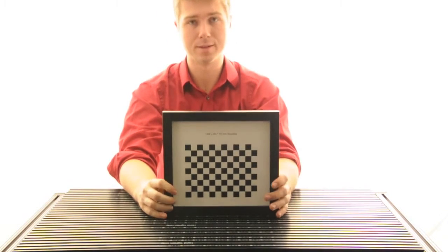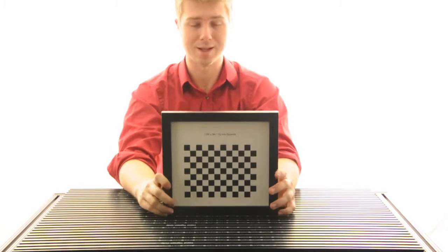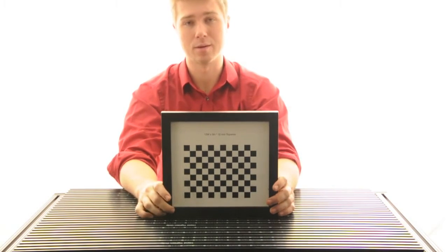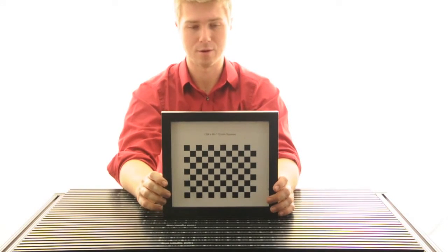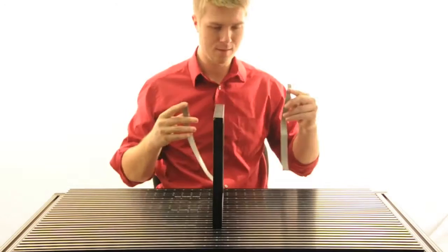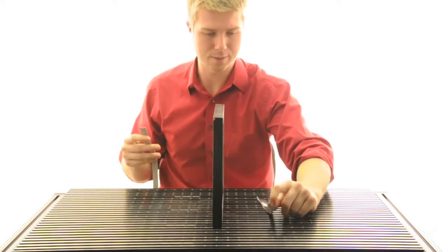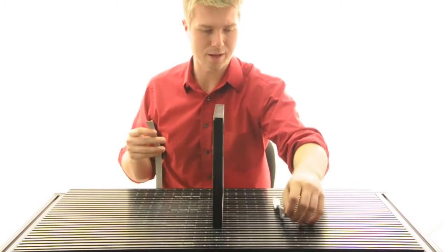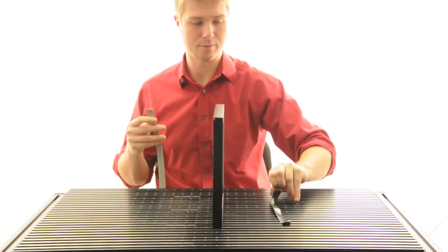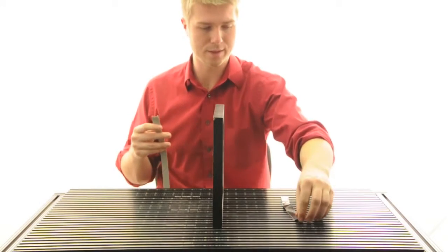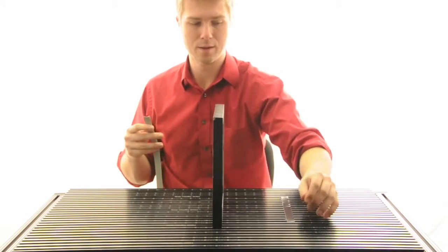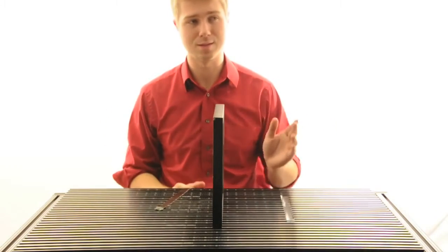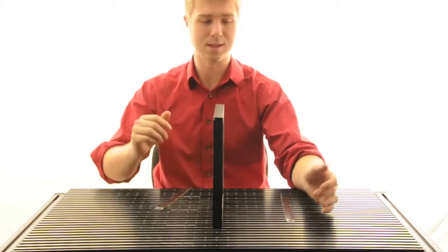For this setup, this calibration, we're going to need a calibration board. The board size is going to vary depending upon which scanning volume you're going to want to set up. Our scanning volume is set up by two different values. First off, we have the width of the lenses from the farthermost position that both of the lenses that we can use in the scanner can see.